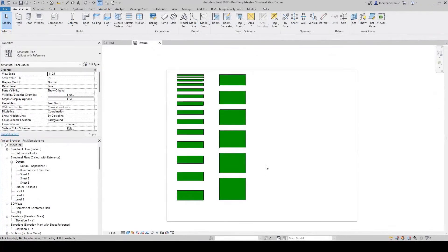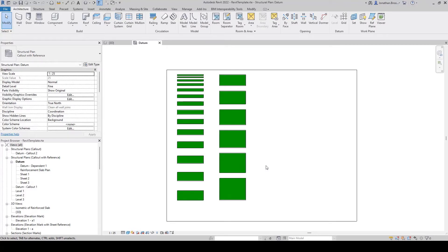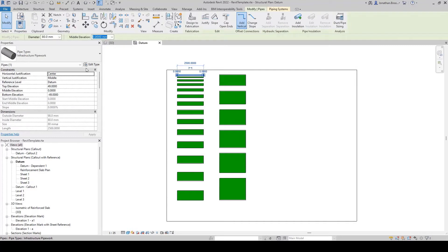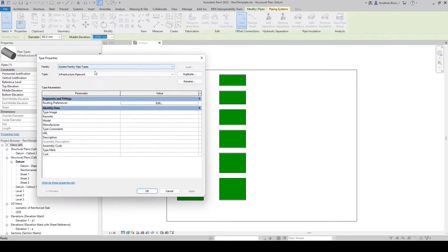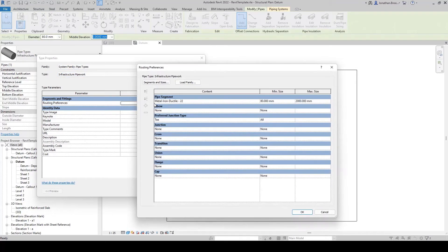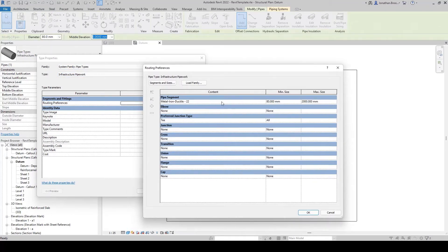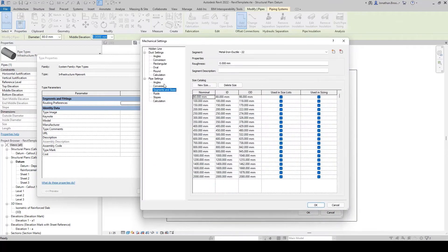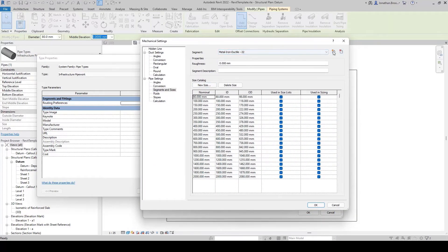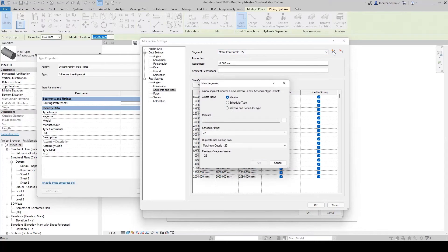Revit allows users to include customized pipe sizes based upon various manufacturers and regional properties. Pipes in Revit work by applying schedules or lists to a particular pipe system family. If we select a pipe and click on edit type, we can change the allowable sizes by editing the routing preferences. If we then click on segments and sizes under the routing preferences menu, we can create a new list of pipe sizes from either a material schedule or type and a combination of both.